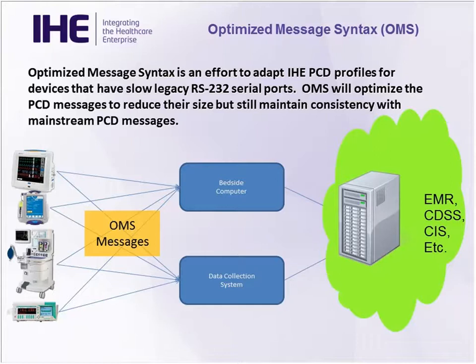While it's not a specific profile, we do have the optimized message syntax message profile. It can be used with any of the profiles such as DEC or IPEC or even ACM to shrink the amount of data communicated from the medical device into the next system up, dominantly being the EMR, but for other purposes as well. The idea is to reduce the load on the serial interface.